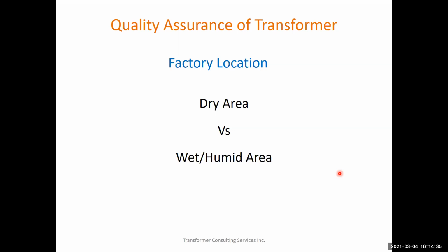Now, if a factory is located by the ocean, due to vaporization, salination from the ocean can land on the transformer, and over time, it can create an ionic path for leakage current to follow. If it creates an ionic path for the leakage current, it can cause failure of the transformer, compromising its quality. So the factory location, whether in a dry or humid area, is very important.